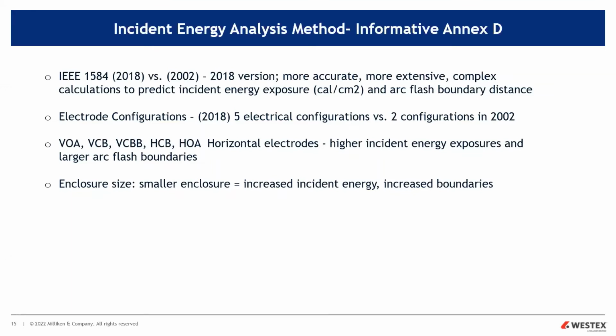So if you have higher incident energies, that could also affect your arc flash boundaries. More energy means it's going to dissipate at a greater distance to get to 1.2 cal, which is your boundary. They also found the enclosure size matters. The smaller enclosure produced higher incident energy. It kind of makes sense: if it's in a smaller package, it becomes more explosive. Higher incident energies possibly increase boundaries, so look at that if you're doing the incident energy method.